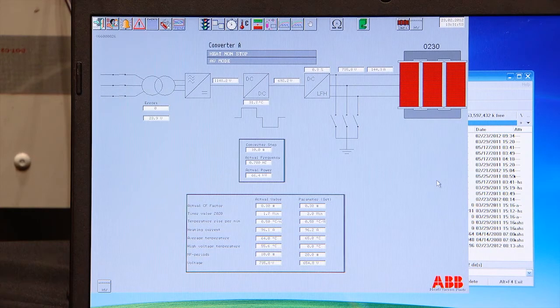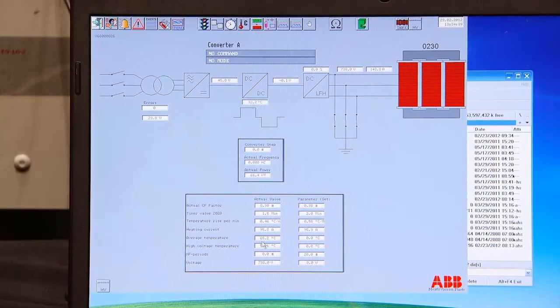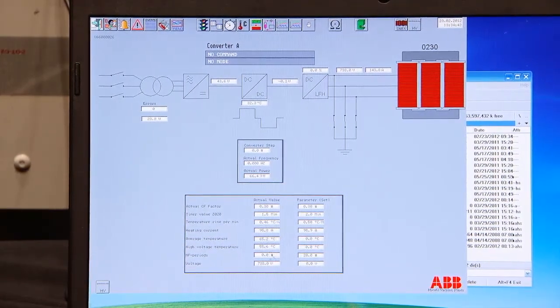If you put it too low, 2 degrees per minute, then it could actually be the measured temperature increase that we do. What you want to catch is if the soldering is bad, if a bad connection, a bus bar is melting or whatever. And if I put 1 degree per minute and you put the alarm level at 1.5 degrees per minute, you never know if it's a bus bar or whatever it is. Right. Five, I'm fine with 5, but I'm not fine with 2. 2 is too low, yes. If I make a slight mistake in the reading of the resistance in the converter, then you have an alarm which you do not know if it's coming from the converter, from the measurement, or... So, we reached 65 degrees, as expected. Everyone's happy.